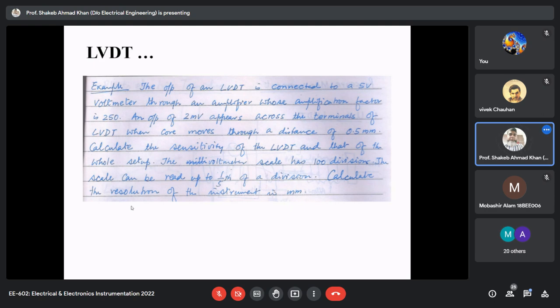This problem has two parts. In the first part, the output of an LVDT is connected to a 5-volt voltmeter through an amplifier whose amplification factor (gain) is given. An output of 2 millivolt appears across the terminals of the LVDT when the core moves through a distance of 0.5 millimeter. So in the first part, you are required to calculate the sensitivity.